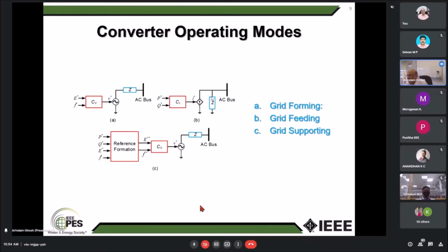However, these grid feeding converters have a problem: they can work in parallel with the grid, but if the grid goes away, they have to switch off. Suppose the grid trips—where are you going to inject the power? So unless you stop immediately, there will be a collapse. They can work in parallel with the grid, but they cannot work without it. Whereas with grid forming, if you have a load, you can keep supplying the load even if the grid goes off.